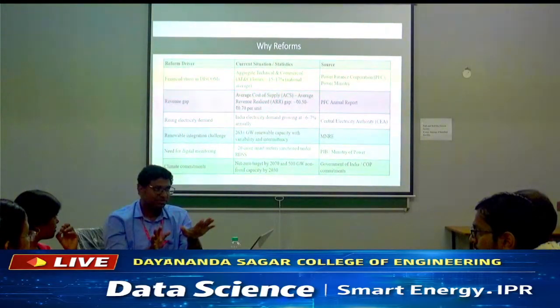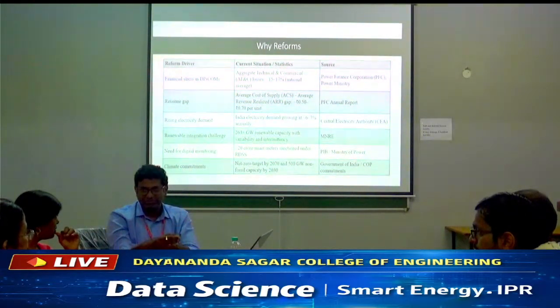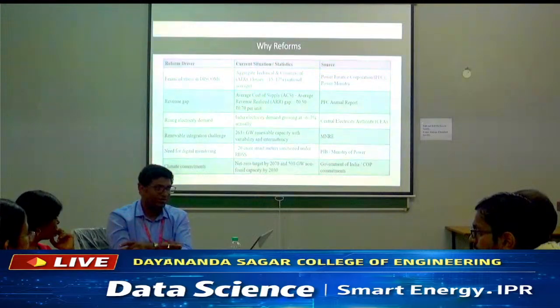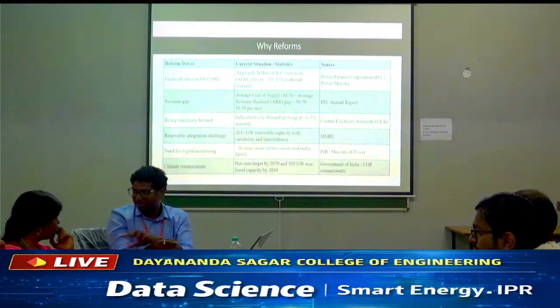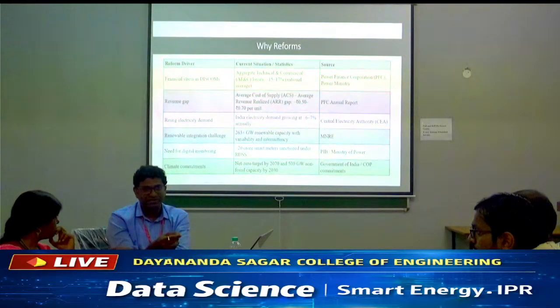Any feeder you cannot terminate to the lower feeder. Why? Suppose some breakdown occurs and the relay trips, immediately back feeding will occur, and the person working in the solar photovoltaic system may get a shock or something will happen. So always try to terminate at the highest outgoing feeder.